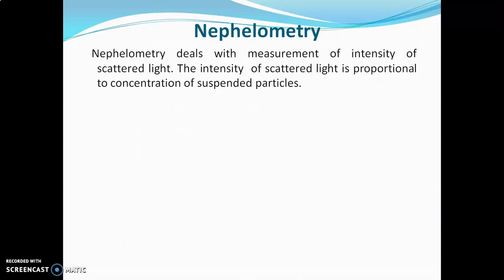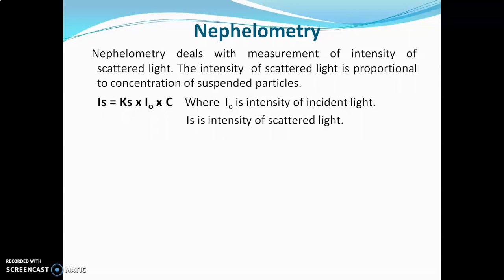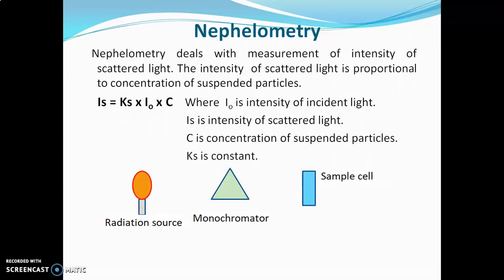Nephelometry deals with measurement of the intensity of scattered light. The intensity of scattered light is proportional to the concentration of suspended particles. The equation is: Iₛ = Kₛ × I₀ × C, where I₀ is the intensity of incident light, Iₛ is the intensity of scattered light, C is the concentration of suspended particles, and Kₛ is the constant. In nephelometry, the radiation source, monochromator, and sample cell are in a straight line, but the detector is placed at 90 degrees or 45 degrees to the radiation source, because scattering can occur in any direction.